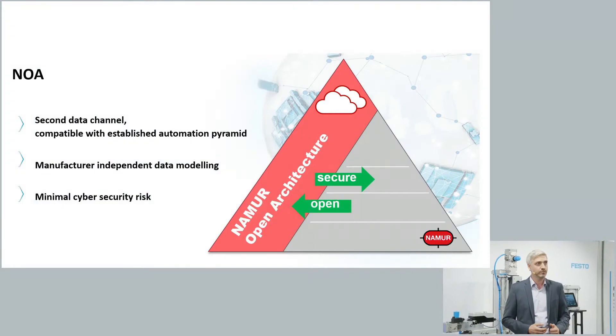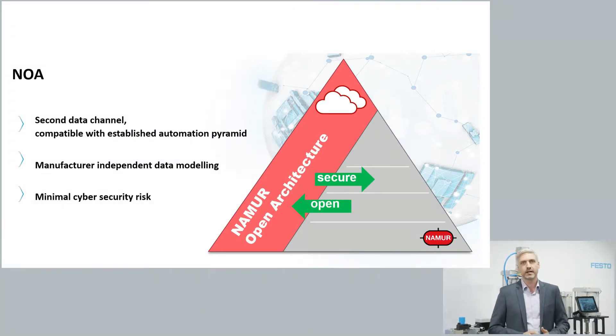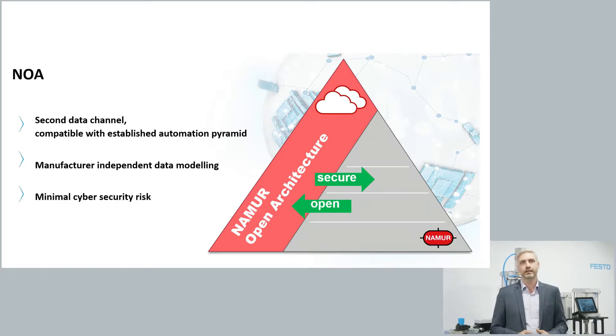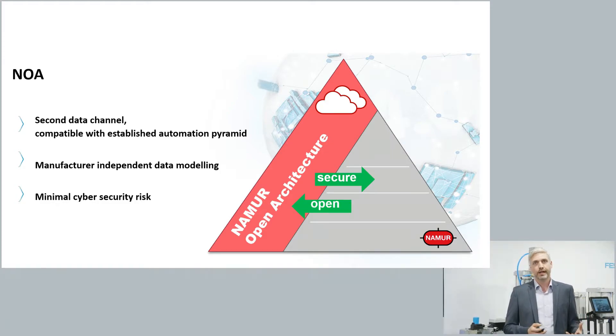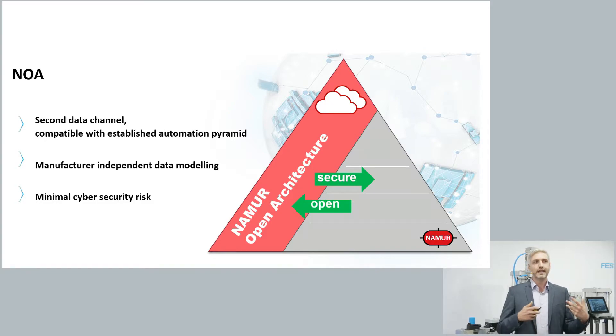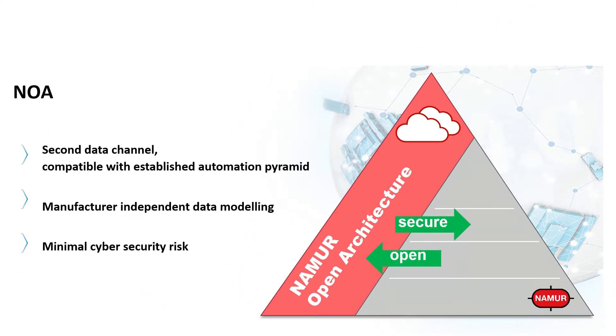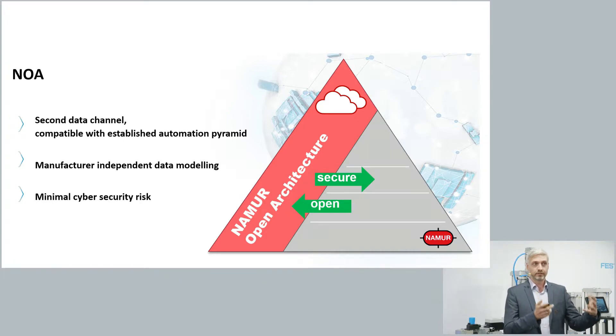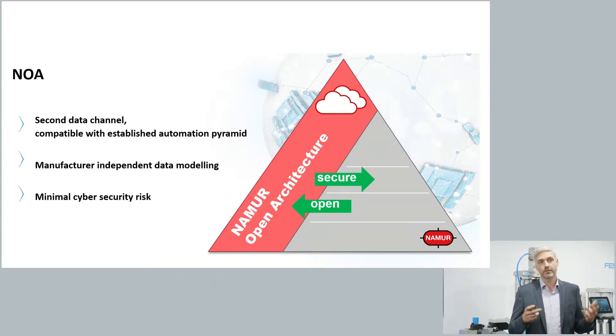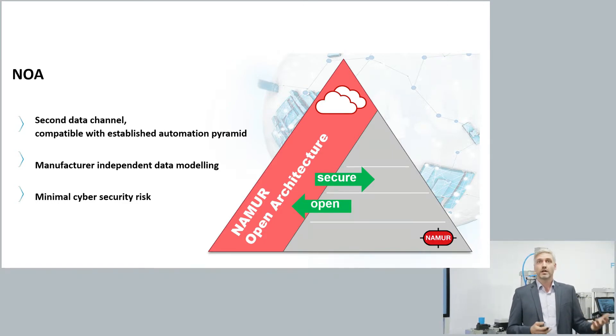Looking at the key aspects of NOA: in the official NAMUR NOA logo you see on the right a gray rectangle representing the established automation pyramid — the core process control. This is then extended with a second channel, the NAMUR Open Architecture domain or NOA domain, where data is computed, transported, and used in optimization applications. The separation of core process control and the data computation domain is a very important aspect of NOA.